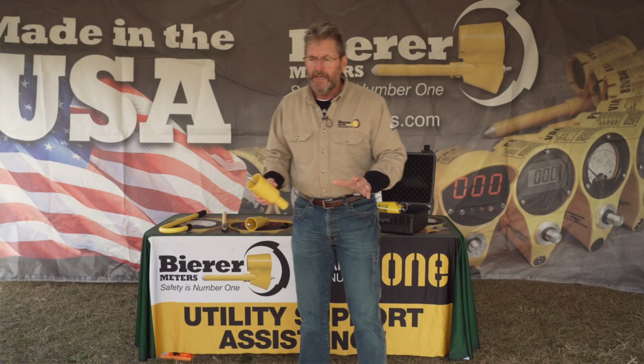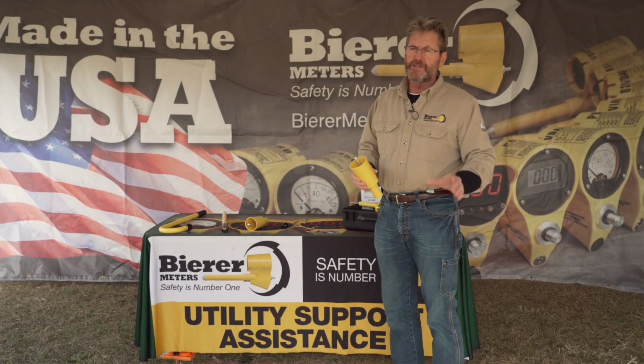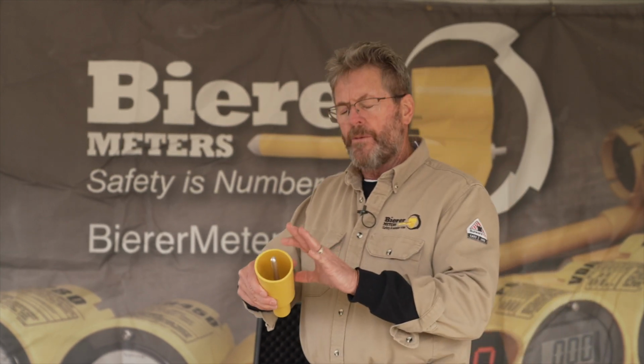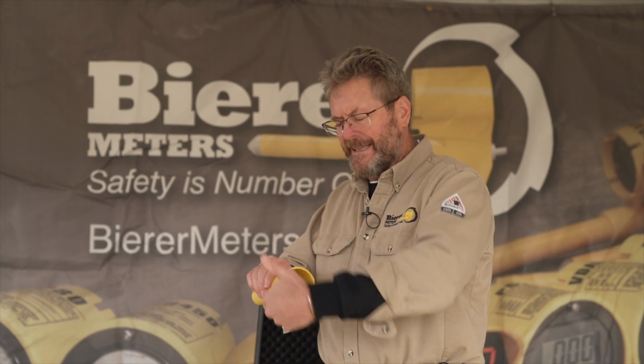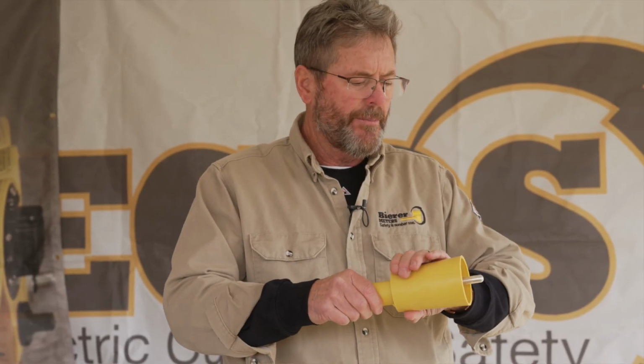It's important, again, to always use the proper Bierer Meters accessory. I was doing some training earlier this year, and they were using a different manufacturer's tool. When they would go through a hot bushing or a feed through, their probe had no isolating characteristics, which Bierer Meters does. We have cover up built around the probe. So the safety we provide for you is much enhanced.